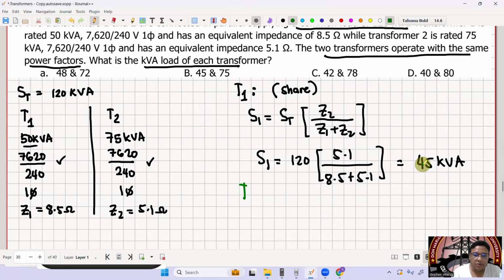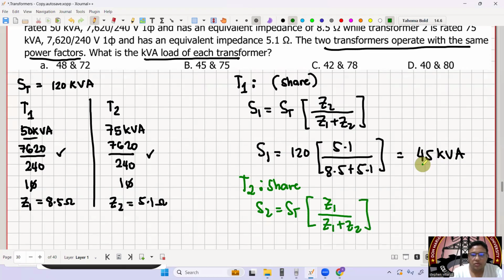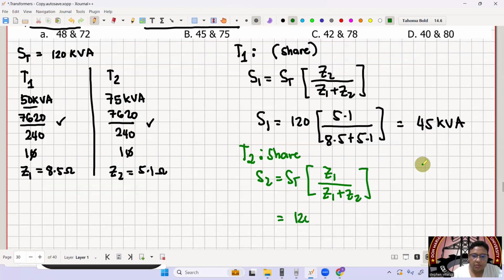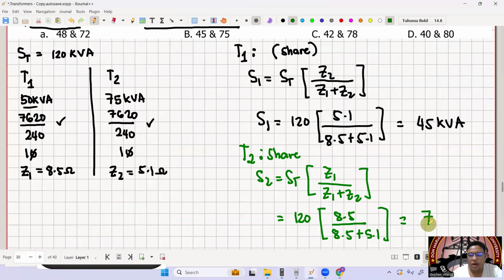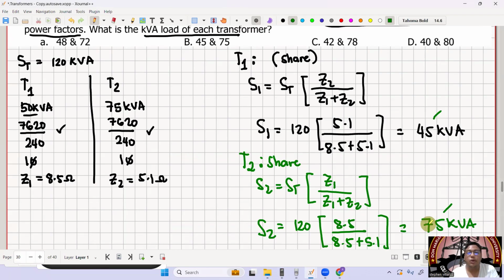Okay, so how about yung T2 share? So, that is now S2 is equal to ST multiplied by Z1 all over Z1 plus Z2. So therefore, ST is 120 multiplied by 8.5 over 8.5 plus 5.1. So palitan lang natin tong numerator dito. Okay, so this is now equal to 75 kVA. So yung share ng transformer 2 is 75 kVA for a total of 120. Okay, kung pag-plusin nyo to, magiging 120 yan. So therefore, this is letter B.